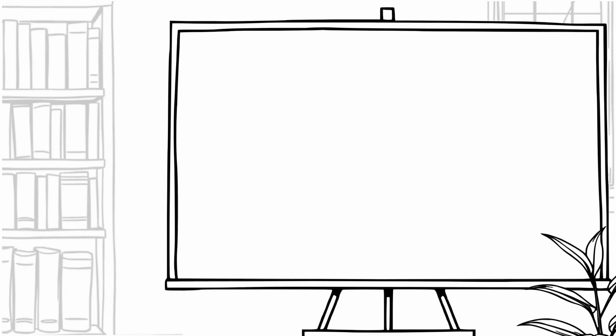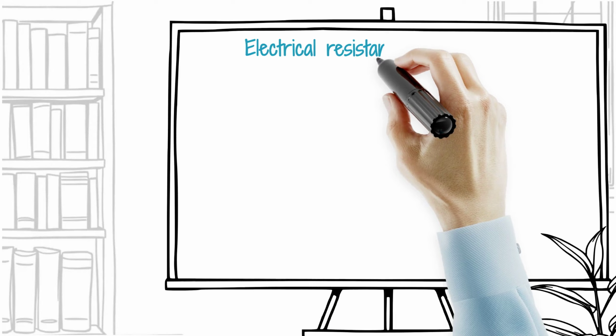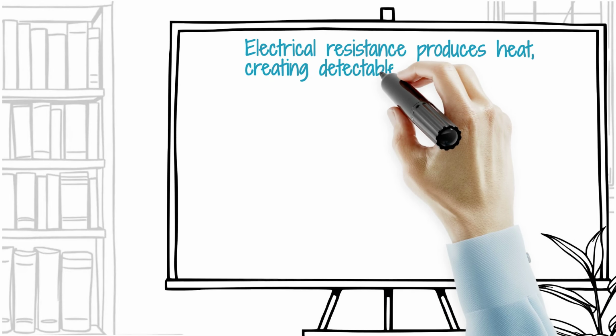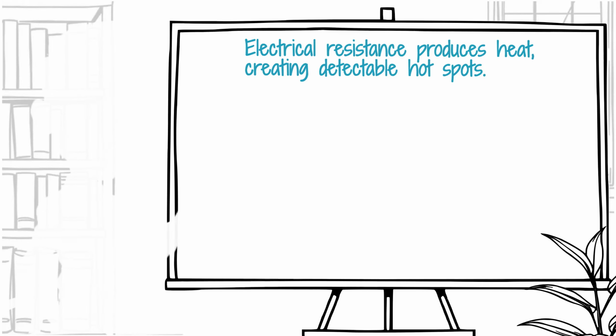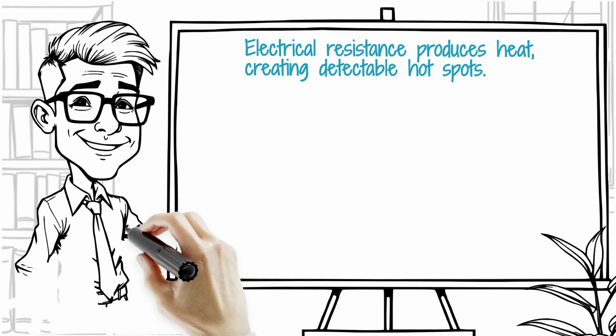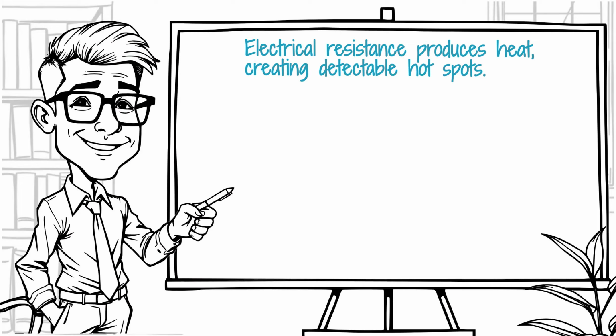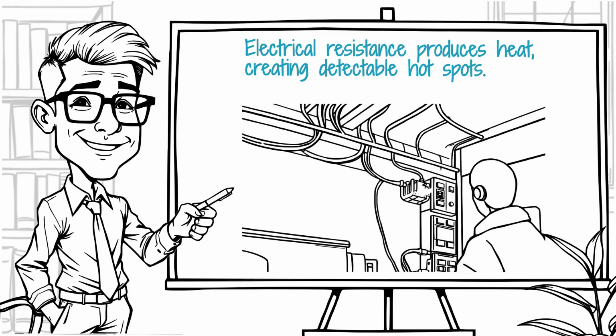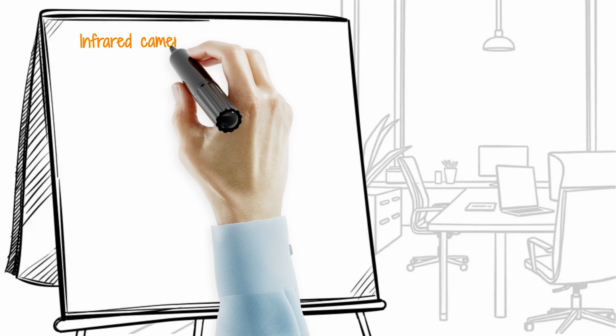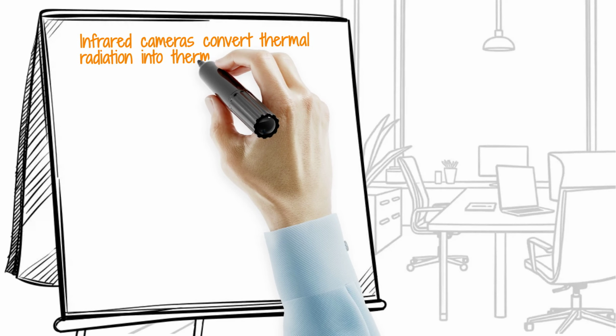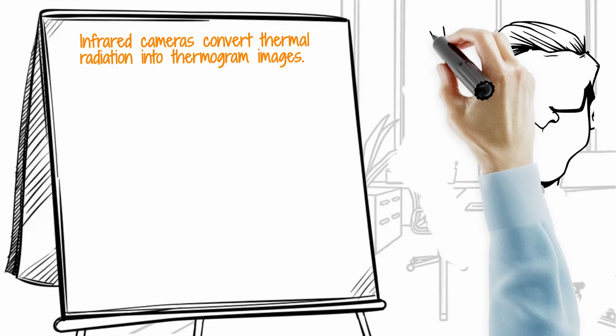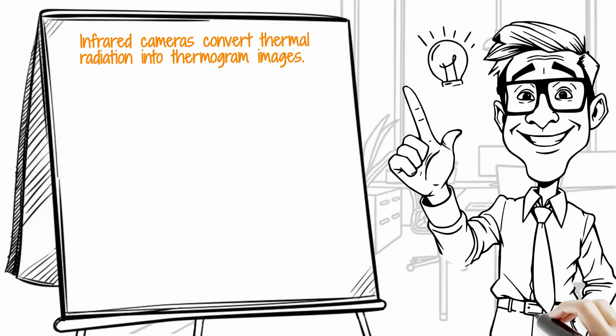The fundamental principle of this technology is that electrical resistance generates heat. When a component such as a circuit breaker terminal or a busbar connection develops a fault, its resistance increases, which in turn produces a localized rise in temperature known as a hotspot. An infrared camera captures the invisible thermal radiation emitted by these objects and converts it into a visible color-coded image called a thermogram.